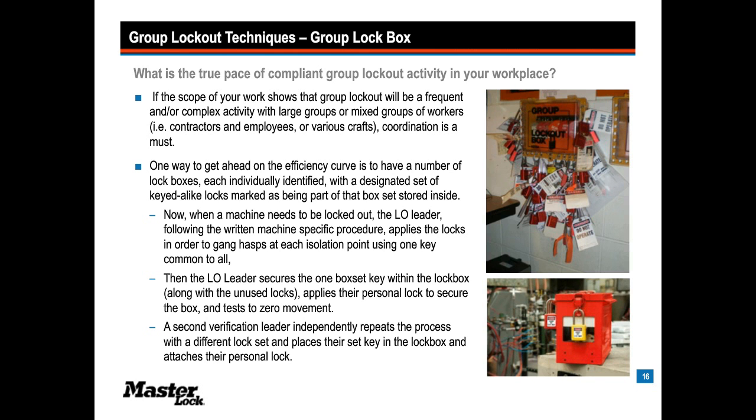People will maybe throw a lock into the mix without really knowing what they're participating in, calling it good enough simply to have a lock in place. So one way to get ahead on the efficiency curve is to set up a series of lockboxes that can be coordinated and assigned to a job. When a machine needs to be locked out, the lockout leader following the procedure could get their locks in place using gang hasps to do the work.